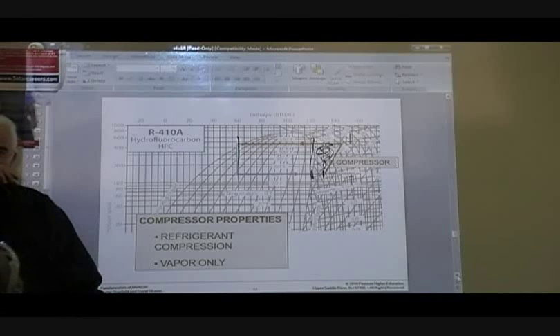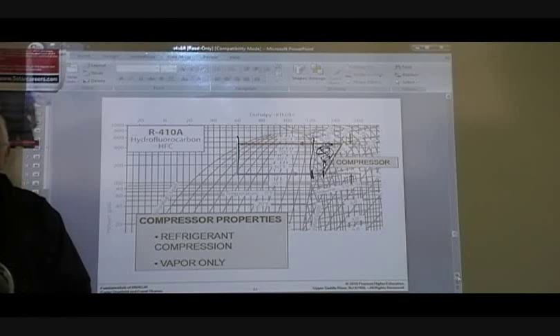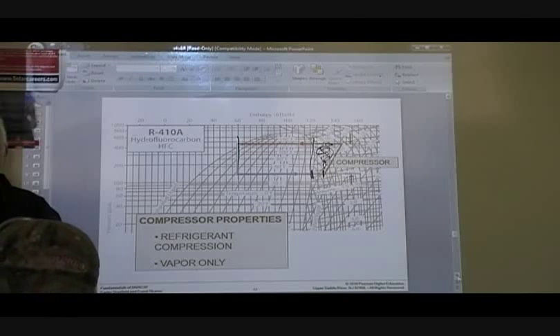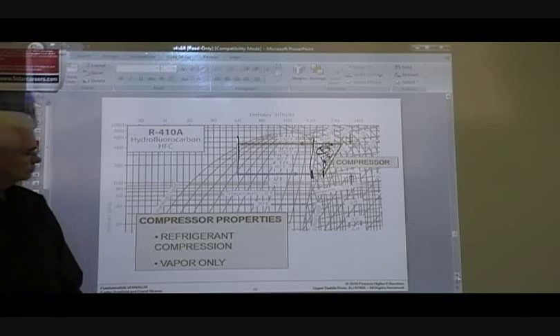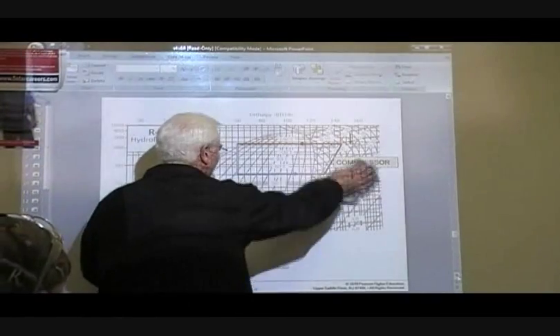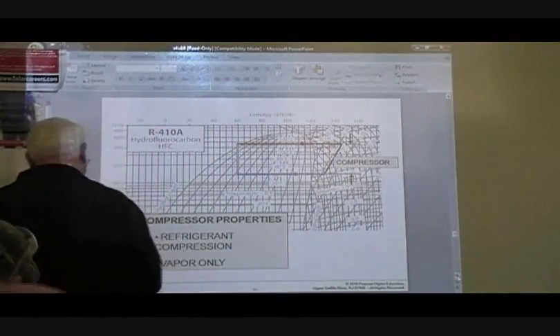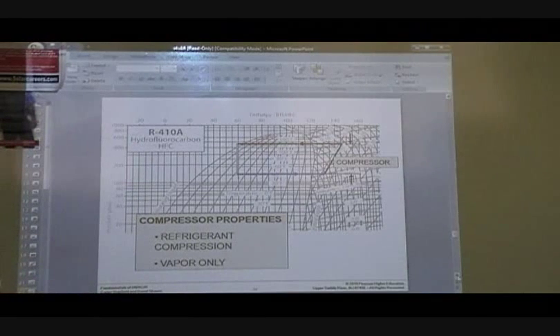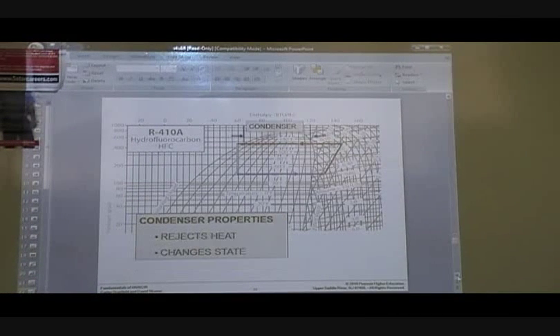No, probably one of the biggest things that you'd do out in the field would be look at your discharge temperature. That would usually indicate whether or not you have a high superheat coming in, plus you may actually have a cylinder or something that's not pumping correctly and recycling the gas back in itself. But the pressure-enthalpy diagram is not something that you would see a lot in the field. But if you know some basic concepts and why it's important and what you can do with it.